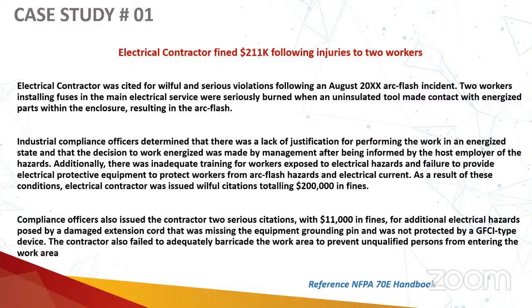That is the basic information, and apart from that, the equipment is not grounded and is not protected with either ELCB or RCCB or GFCI type of device. If there would have been any control on that end, probably that isolator might have tripped and the arc would not have been generated.